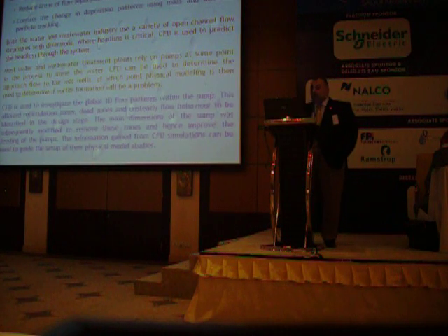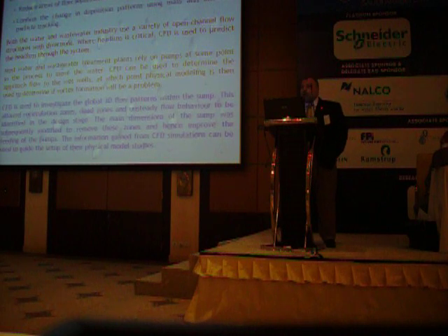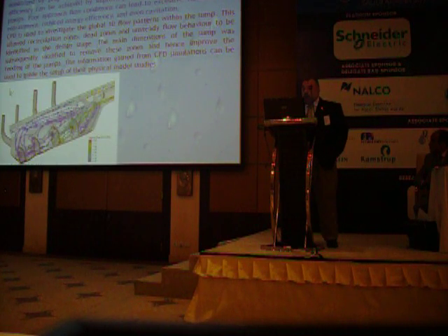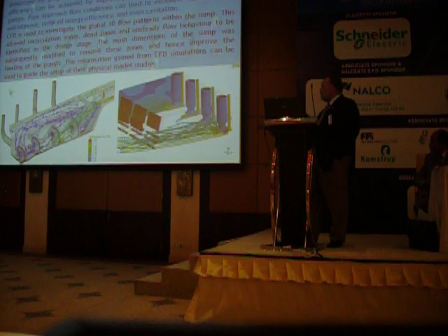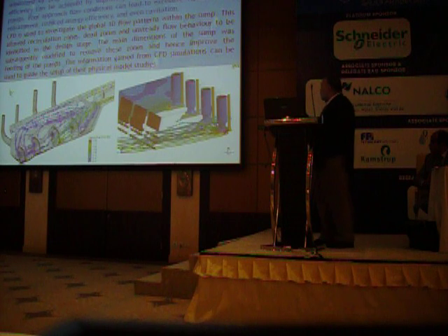If you see some illustrated three-dimensional examples, very common examples any mechanical engineer uses every day, like sumps or recirculation pumps or piping. You will see here for a pump sump, for example, 4 pumps, 3 duty plus 1 standby, and if you see here the streamlines. Some of the engineers like to predict the flow streams and how they can be affected by the velocity. Or if you have 3 pumps and 1 in standby, how the intake behaves.